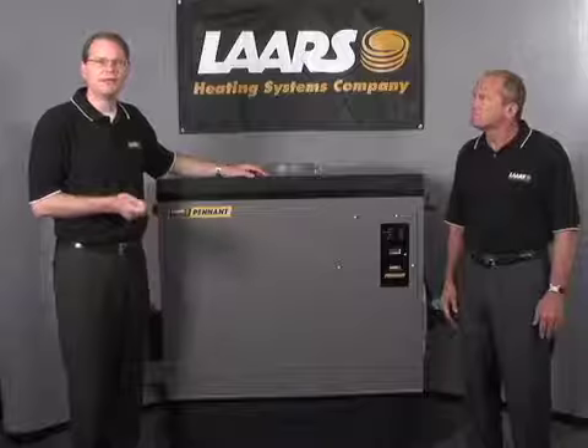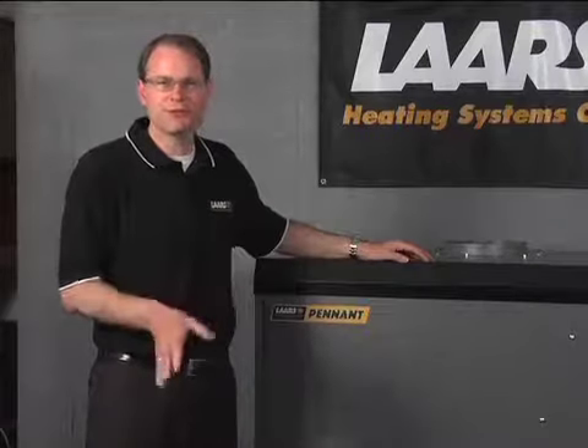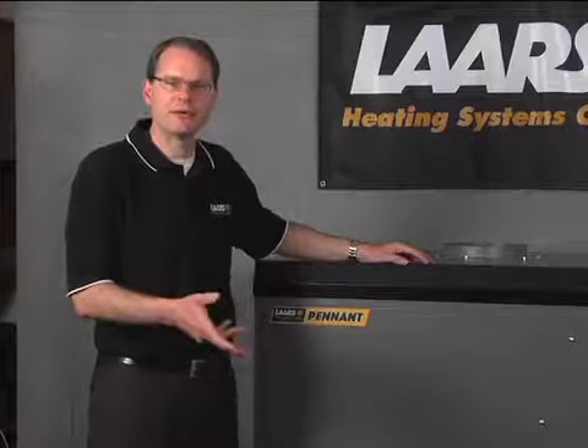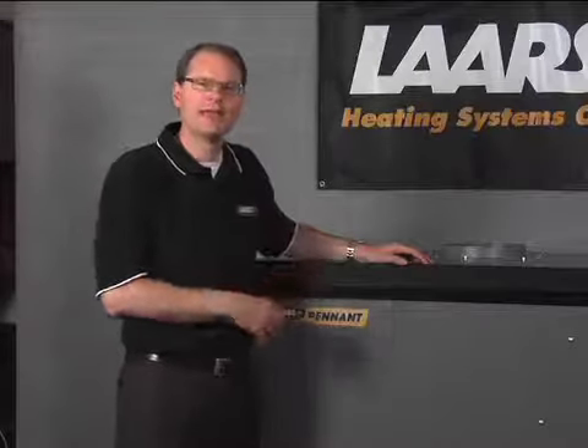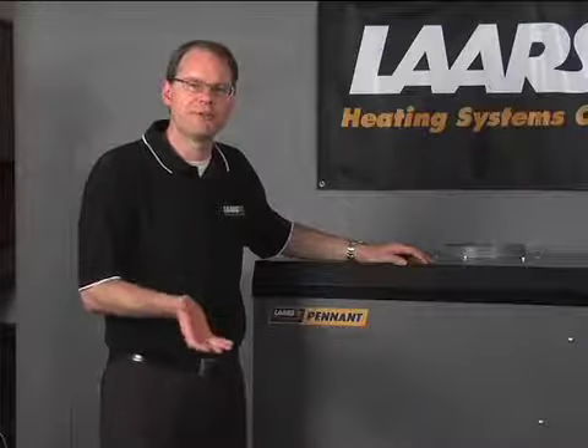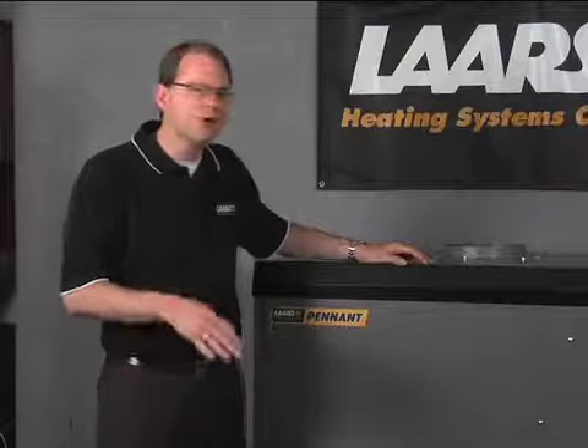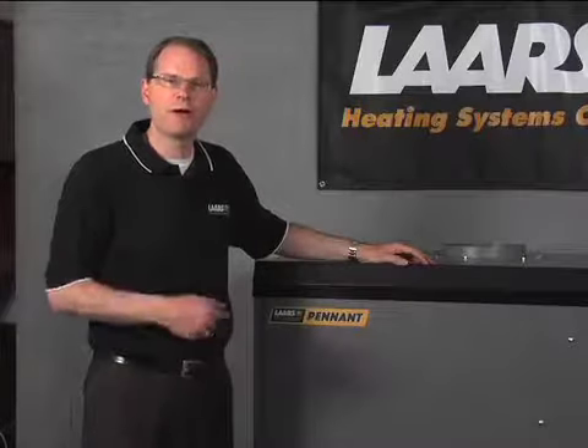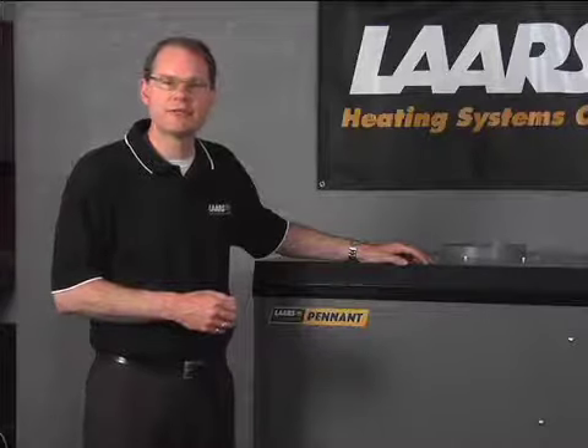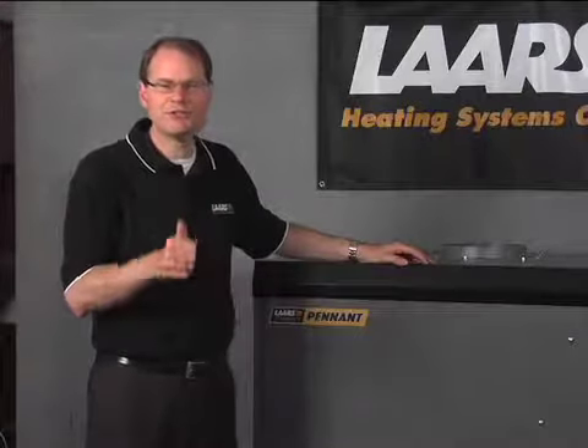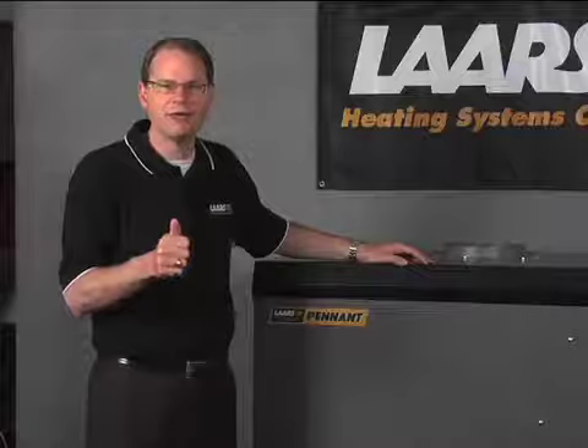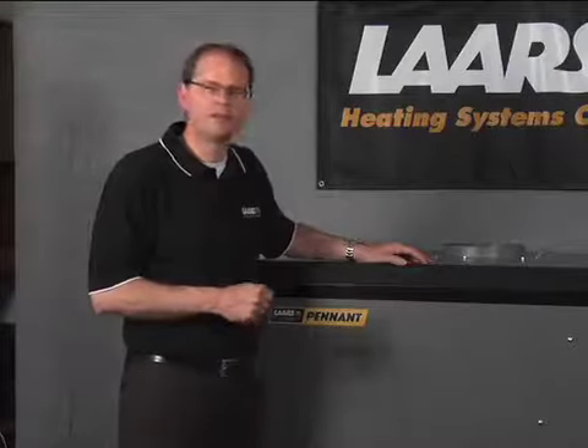Right, and as John was talking about with pool heaters, there's a special subset for pool heating. If you have a salt water pool, not a salt chlorinated pool, but a pool that's actually got salt water in it, you don't want to use a copper fin tube heat exchanger, you want to use a copper nickel heat exchanger. So one of the features of the Pennant is that a copper nickel heat exchanger is available for those salt pool applications, or for domestic water applications where our applications group says that it's mandatory to use copper nickel heat exchangers. So very soft water applications need copper nickel, and sometimes very hard water applications need copper nickel as well.